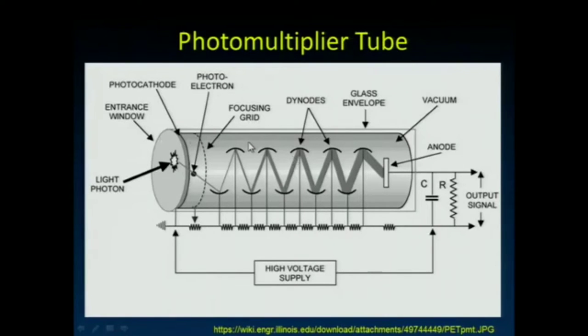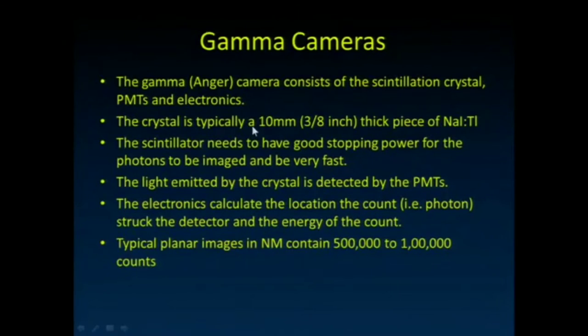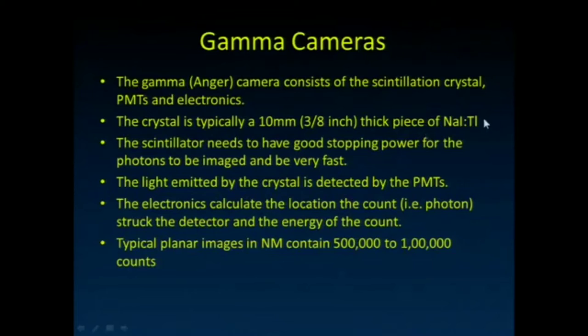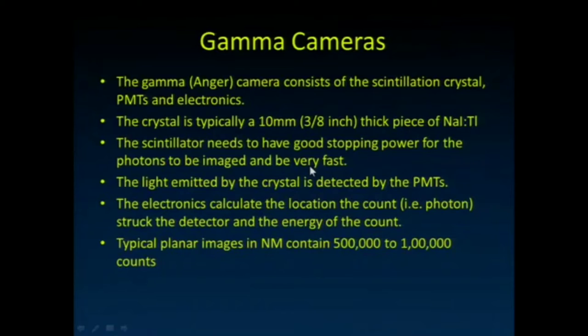The system consists of a scintillation crystal, photomultiplier tubes, and electronics with a collimator mounted in front. The crystal is typically a three-eighths inch piece of sodium iodide doped with a little thallium. This scintillator needs good stopping power for the photons we want in the image, and it needs to be very fast so I can record each event immediately. If it's slow, multiple events will pile up and it becomes hard to distinguish individual events.